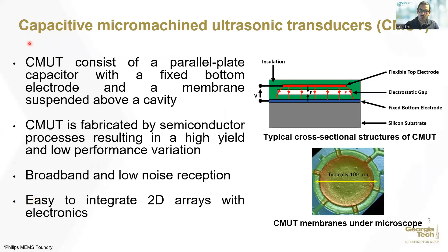To overcome these difficulties, we are working on a new CMUT array design. To explain CMUT technology briefly, it has vibrating membranes including conductive electrodes. Due to their dimensions, they are fabricated in standard semiconductor processing. As you can see in the figure bottom, depending on operating frequency, they have hundreds of micrometer diameter membranes and micrometer-level electrostatic gap sizes. One of the biggest advantages of this technology is that they can be operated broadband frequency with a low noise reception feature. Moreover, easy integration with electronics makes CMUTs more functional.